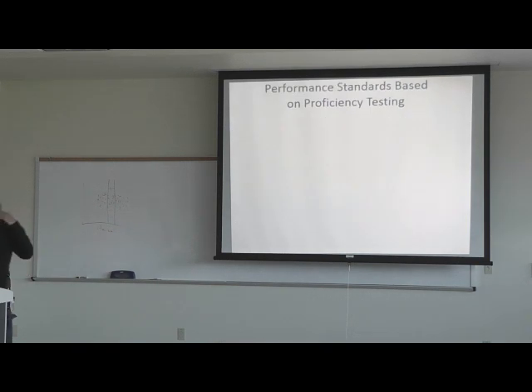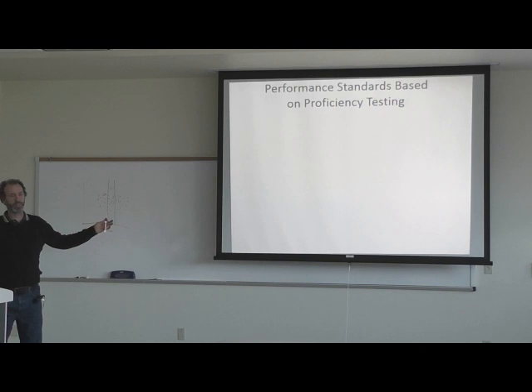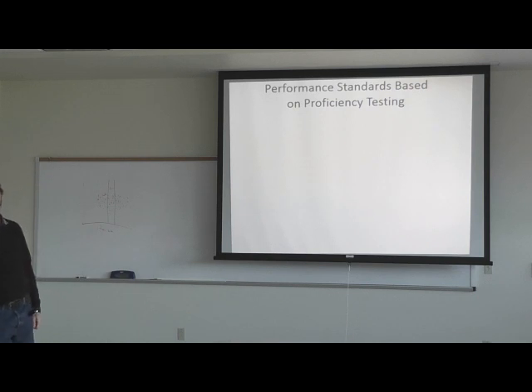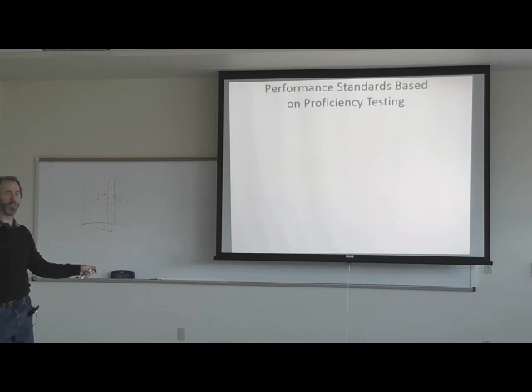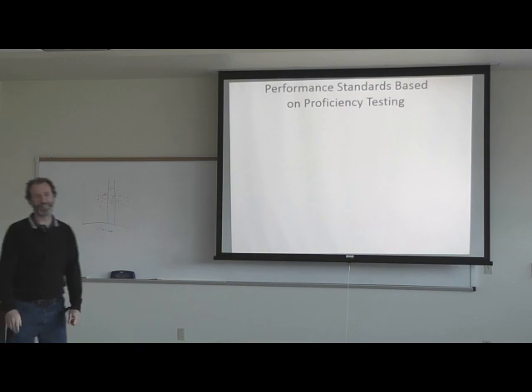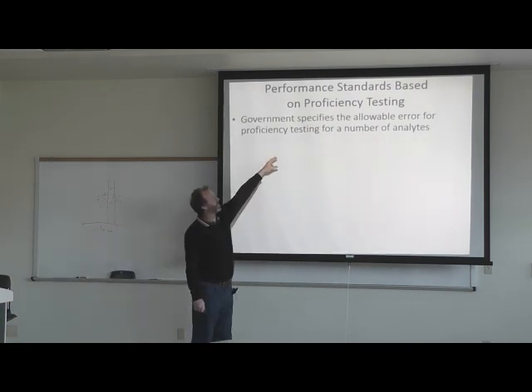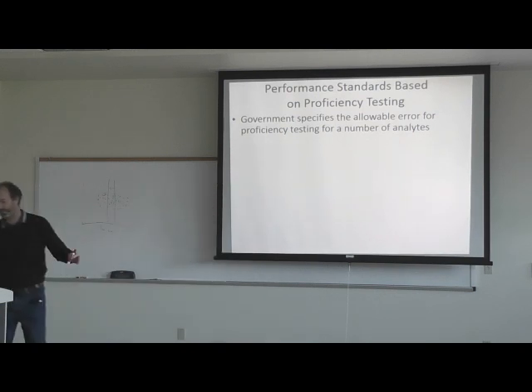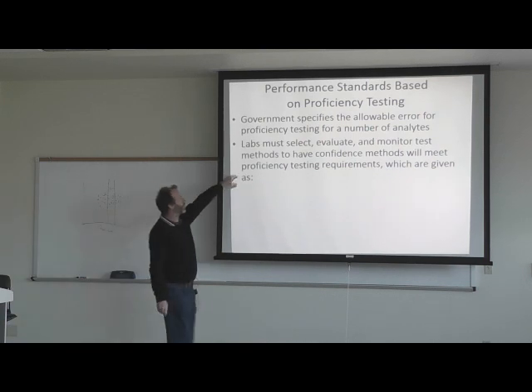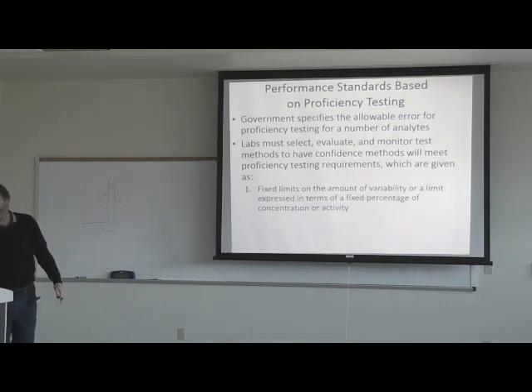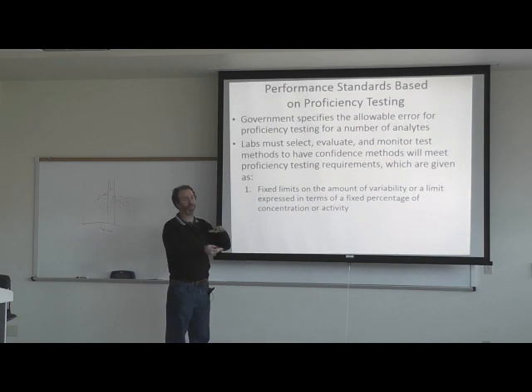Performance standards based on proficiency testing: those are outside groups like CAP that give you samples and test how well you do compared to your peers. The government specifies the allowable error for proficiency testing for a number of analytes. Labs have to select, evaluate, and monitor test methods to have confidence the methods will meet proficiency testing requirements, given as fixed limits on the amount of variability or a fixed percentage of the concentration or activity.